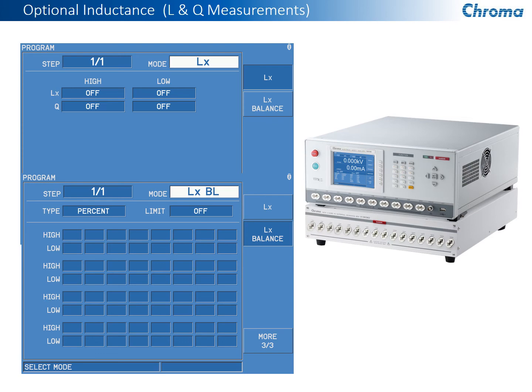And by doing this, we can not only measure the inductance of each winding, but then compare it and use a limit for each of those as well to make sure they're closely balanced with each other. Another test that can be performed with this is the quality factor. We can also measure quality factor with the LCR meter attached.